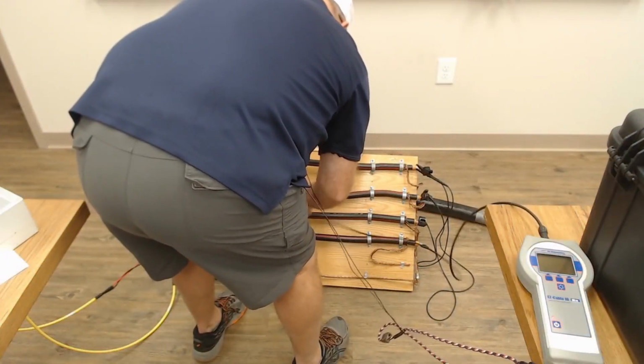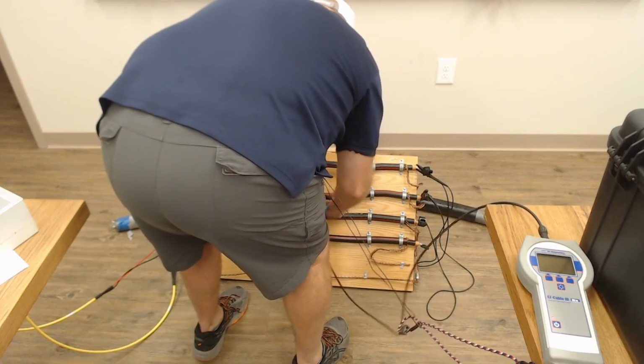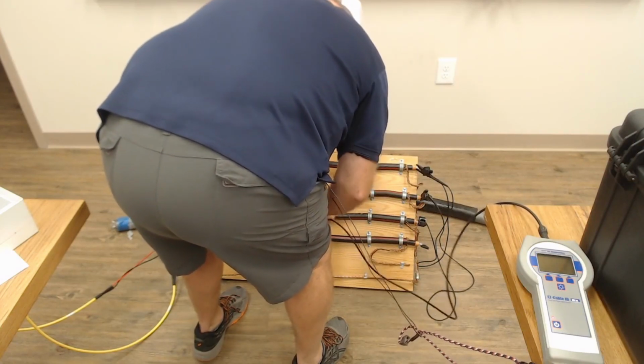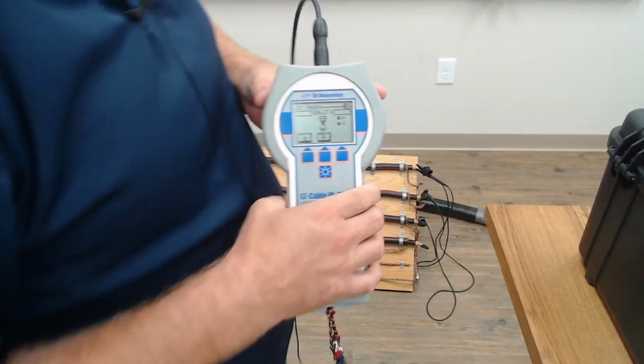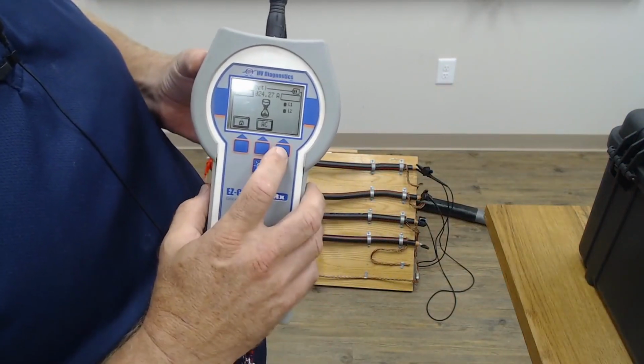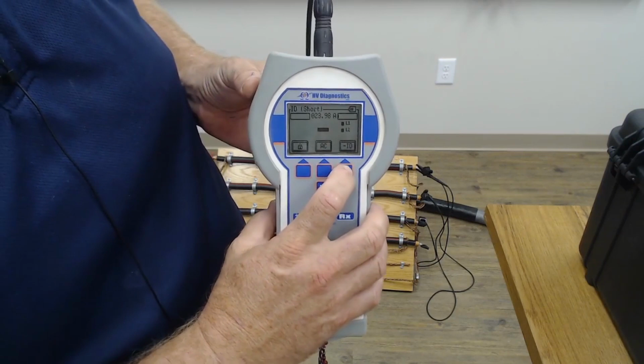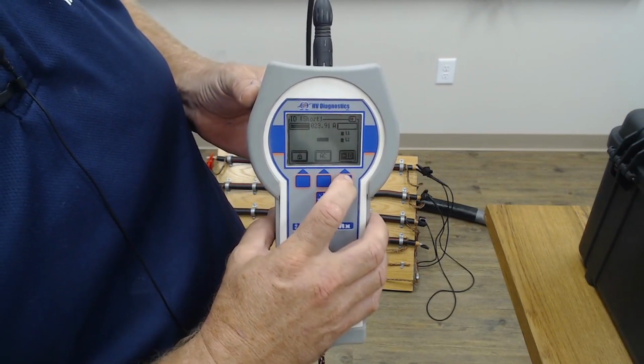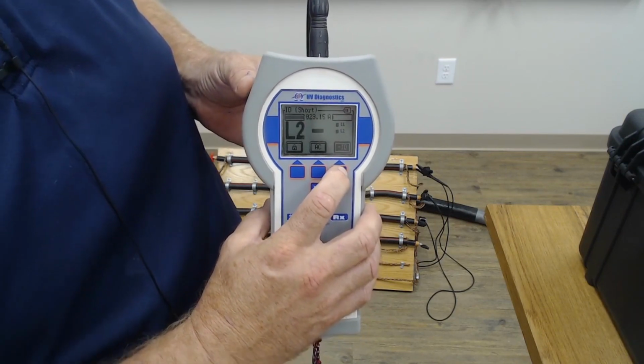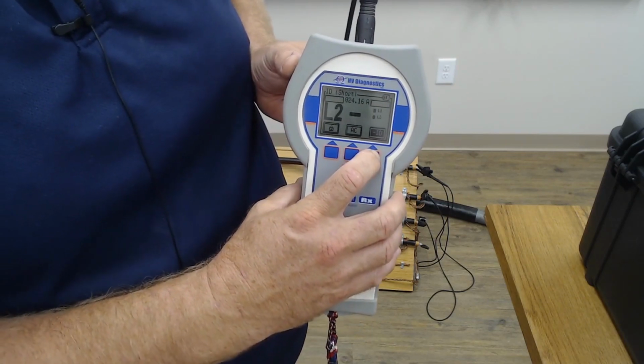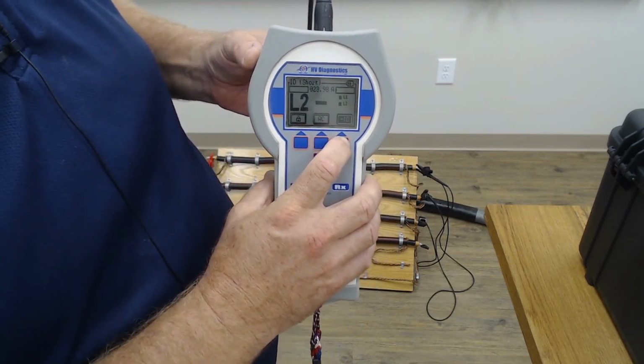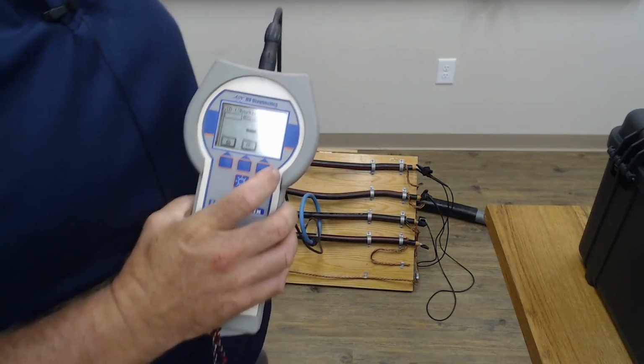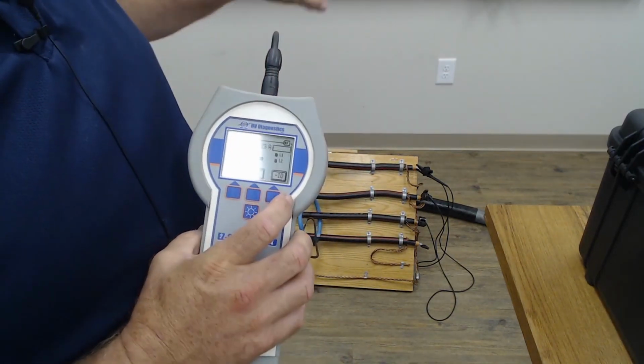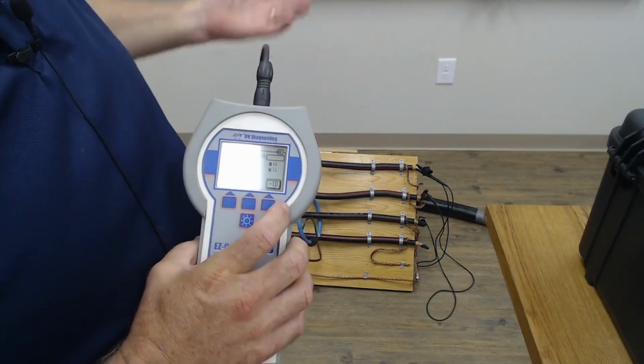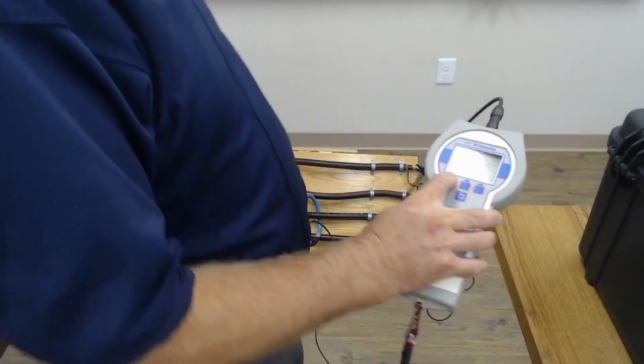And then finally, on the returns on C phase, which will be perfectly correct, it'll be unique to the C phase, we should have a big negative. And that big negative means that's your returns on C phase. And there's your big negative, and we press L1. You can see there's L1 in there and an L2, both flowing in the negative direction. In other words, that's exactly what we want to identify C phase. So there you have it on a three-phase cable. Now we'll show you later on a longer cable, not a short board like this, but the same principles apply.